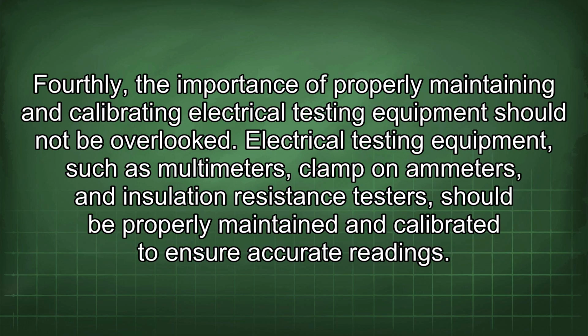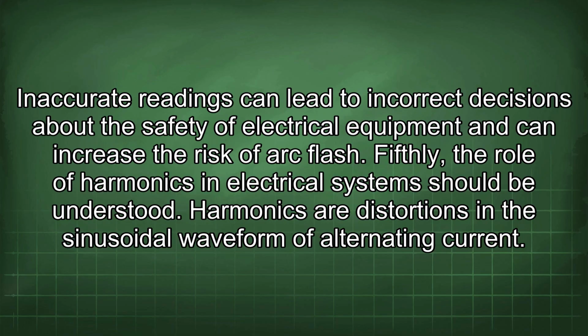Fourthly, the importance of properly maintaining and calibrating electrical testing equipment should not be overlooked. Electrical testing equipment, such as multimeters, clamp-on ammeters, and insulation resistance testers, should be properly maintained and calibrated to ensure accurate readings. Inaccurate readings can lead to incorrect decisions about the safety of electrical equipment and can increase the risk of arc flash. Fifthly, the role of harmonics in electrical systems should be understood.